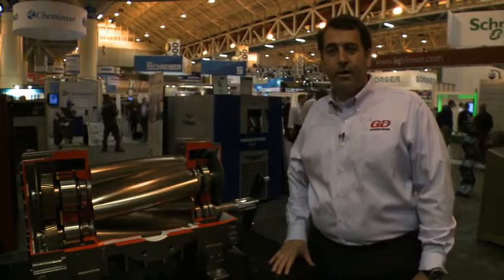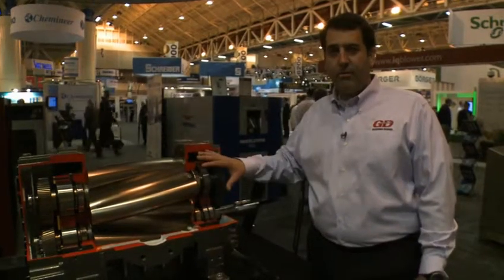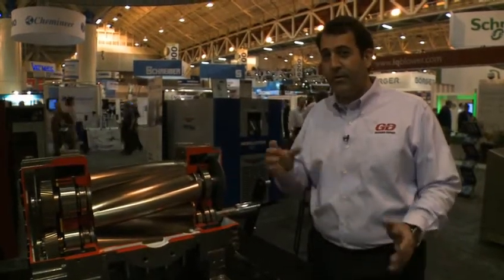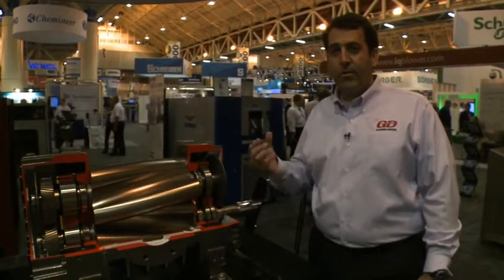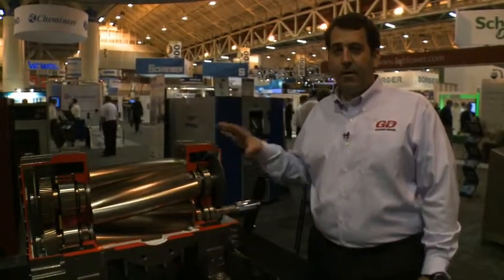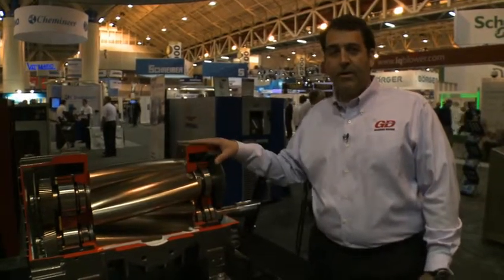So this is the HeliFlow line. It's available in 6 different sizes. This is the 514, our latest model. It goes between 500 CFM and roughly 1200 CFM. Our largest machine, the 624, goes to 3000 CFM. They are all 15 PSIG machines, so they're very robust and have high overhung load.